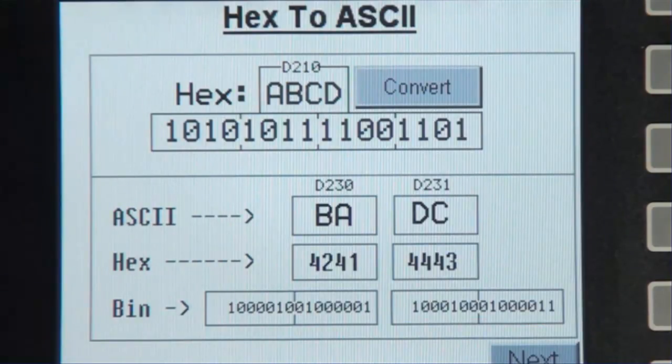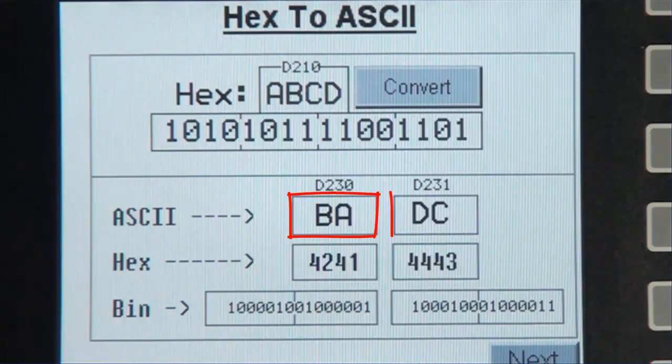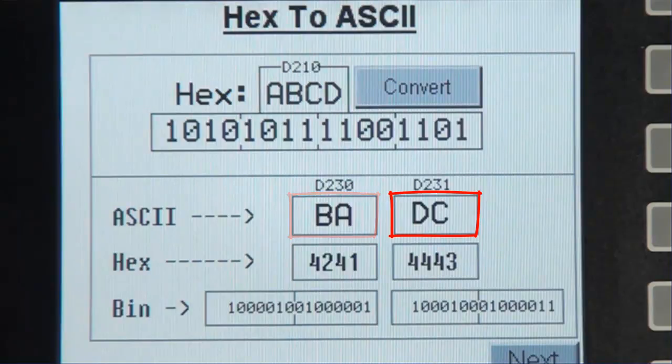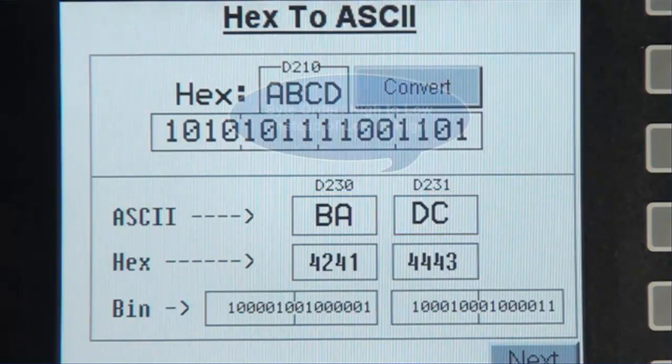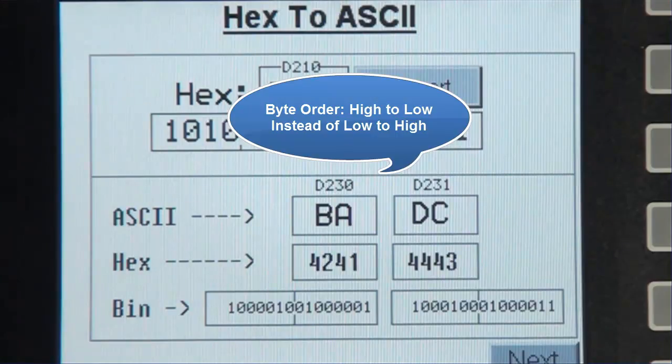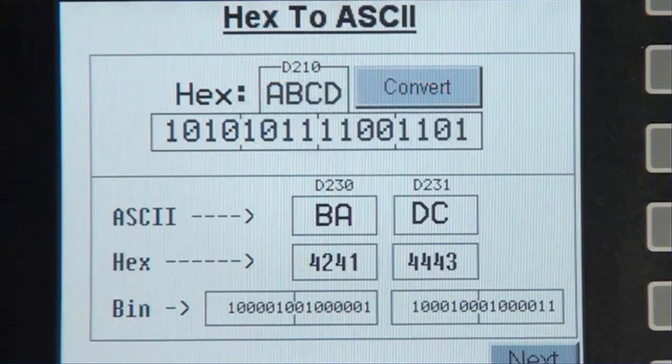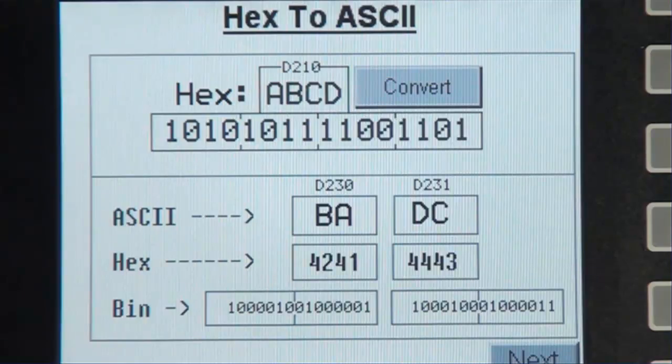Now notice the value in the ASCII register. It's BA instead of AB, and that's because we decided to use the byte order of high to low instead of low to high. This option can be changed in the register's properties.